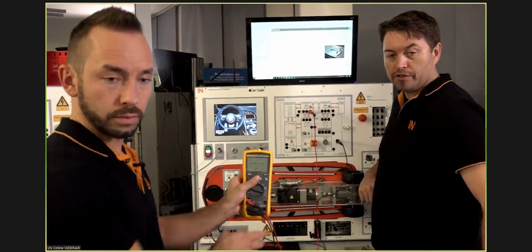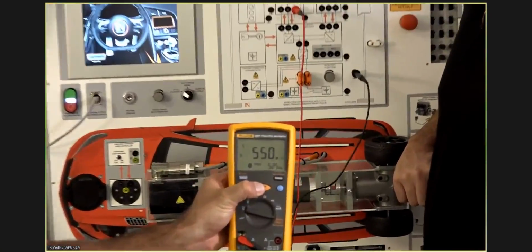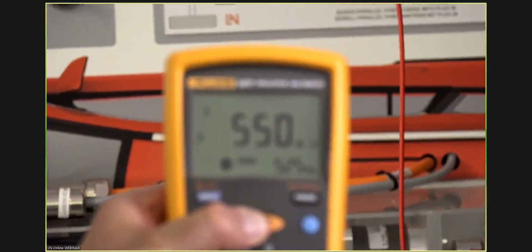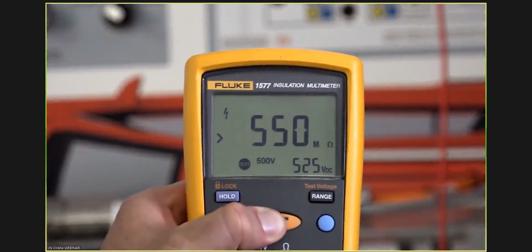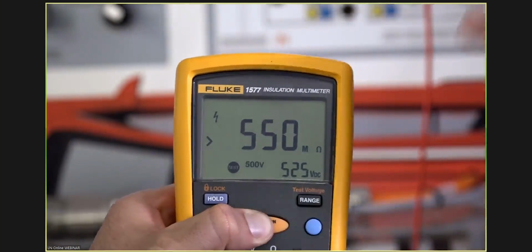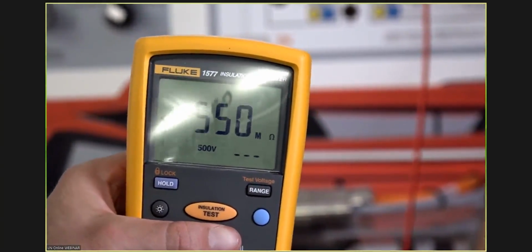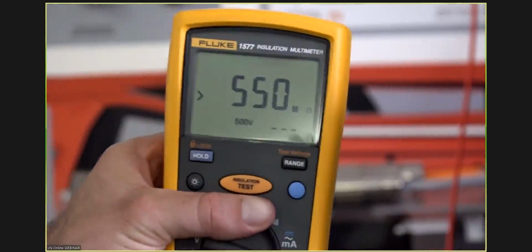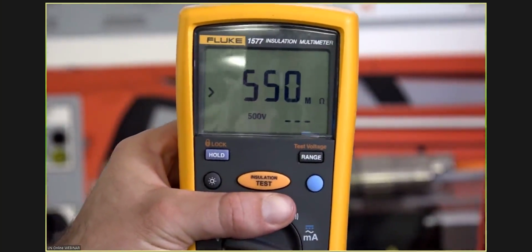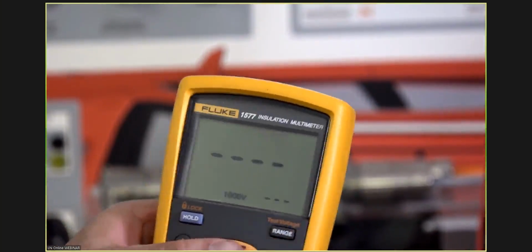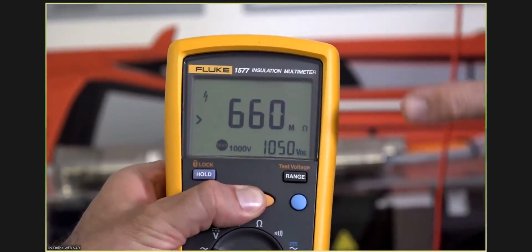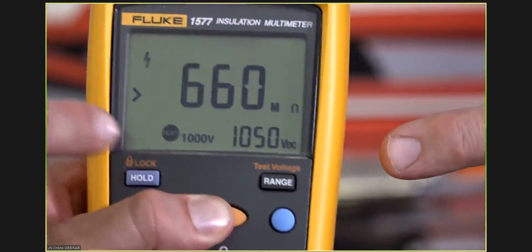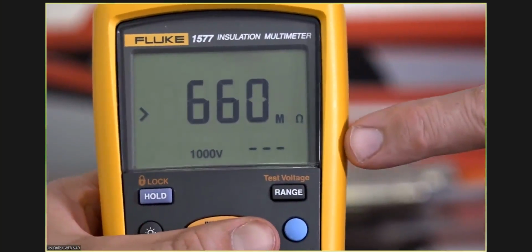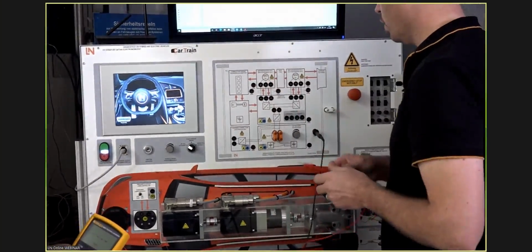So, can I go? Yep, do the test and we can see. What that's doing is putting out 1,000 volts between here. Now we're running onto motor generator 1 and the ground. What that's telling us is it's giving us both a voltage and a resistance reading. So 500 megaohms, 550 megaohms above. That's actually the limit of the device. So it's well above. At 500 volts it's showing 660 megaohms. I'd switch now to 1,000 volts then. Yep, so 1,050 volts is where it got to, and it still didn't break down. So we've got insulation resistance to that. That's telling us that motor generator 1 is fine.